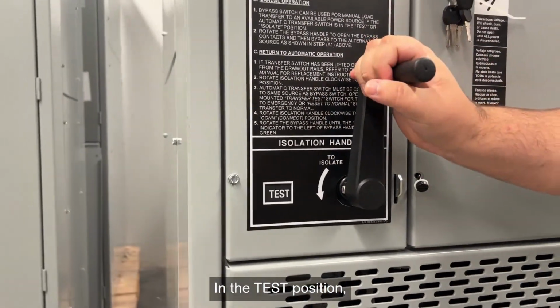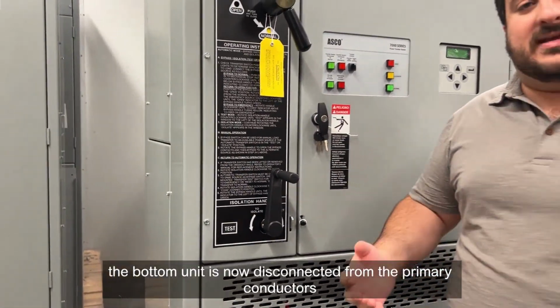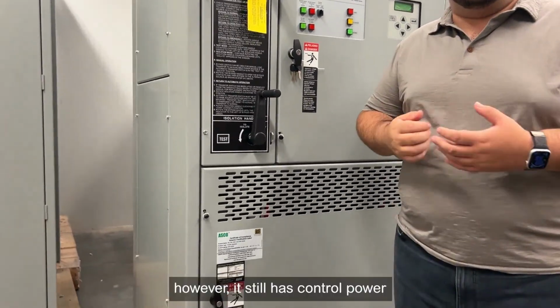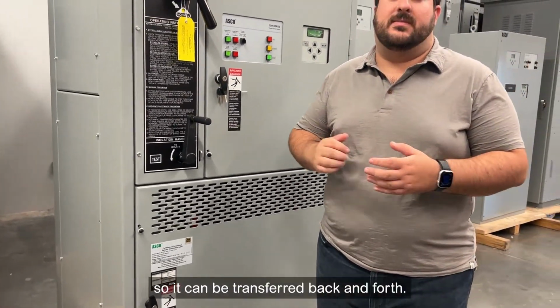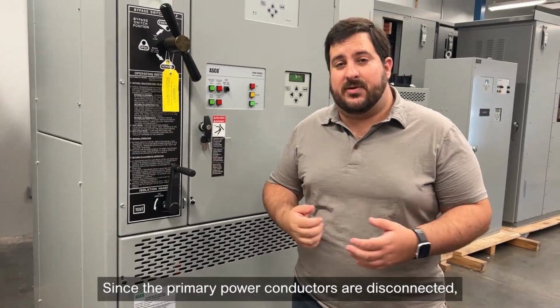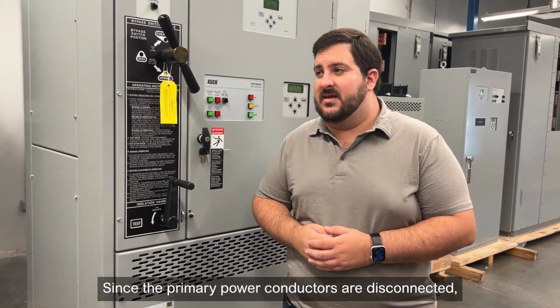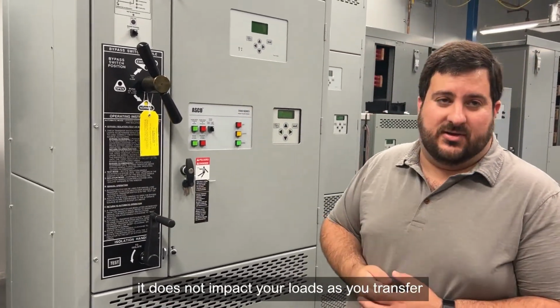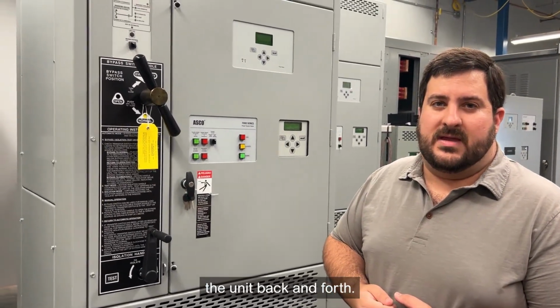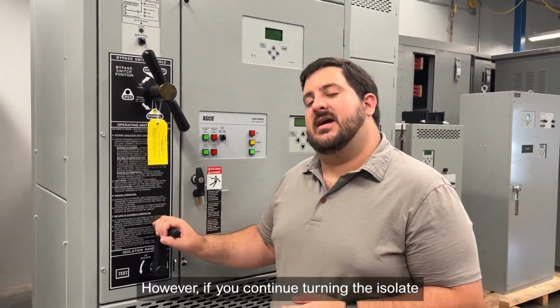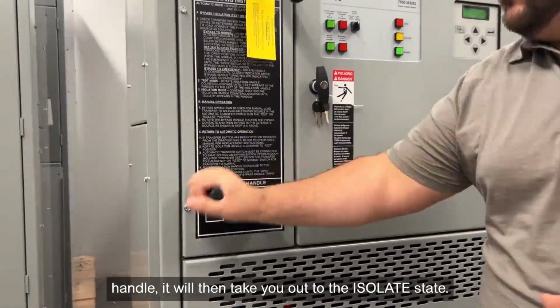In the test position, the bottom unit is now disconnected from the primary conductors. However, it still has control power, so it can be transferred back and forth. Since the primary power conductors are disconnected, it does not impact your loads as you transfer the unit back and forth. However, if you continue turning the isolate handle, it will then take you out to the isolate state.